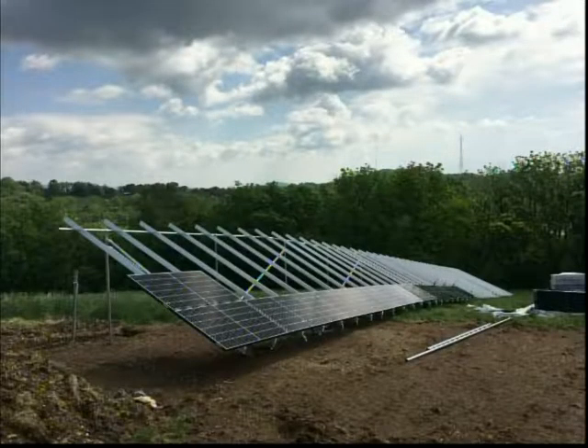So, can you explain to everybody what a microinverter is and how it works a little bit? Sure. A microinverter is an inverter, but it's micro, meaning it's about the size, I always say, of a small ham sandwich that goes underneath each solar panel. Like I could show you in this picture, there's racking that goes up, and on the racking we bolt inverters, and then the solar panel sits over top of each inverter, connected with DC wires. In this case, these are 40 volt, 315 watt solar panels, and that gets plugged, two plugs, positive and negative, into the small inverter.